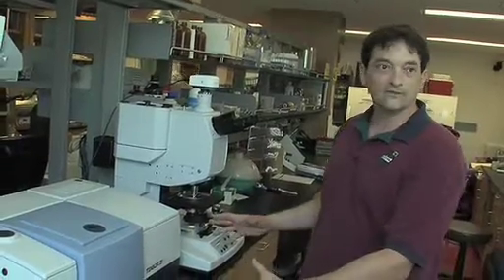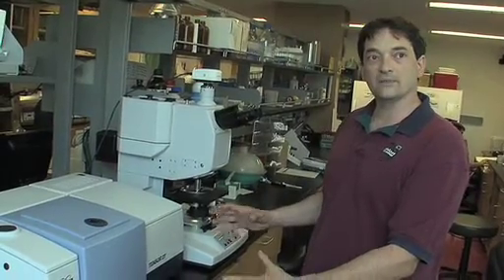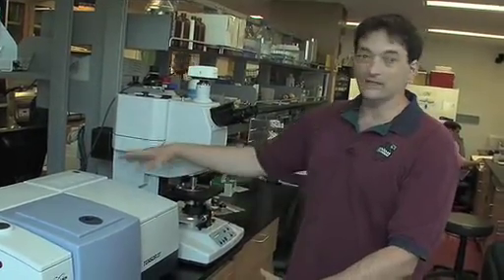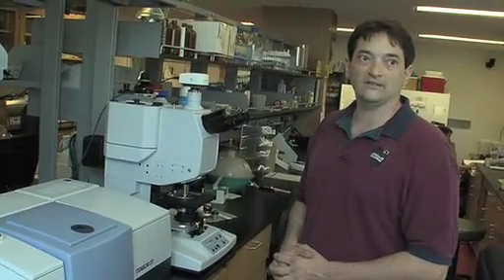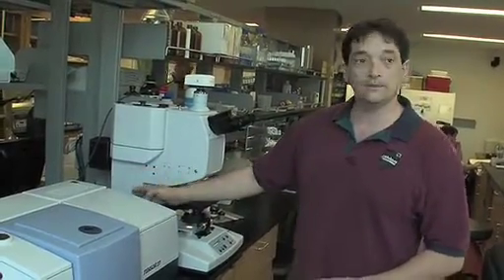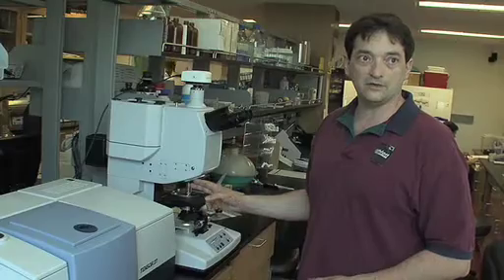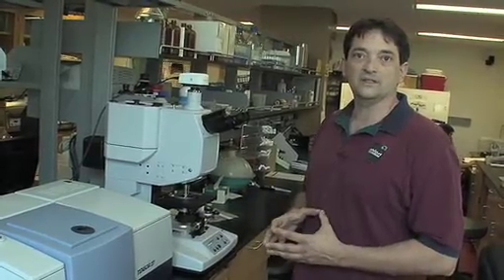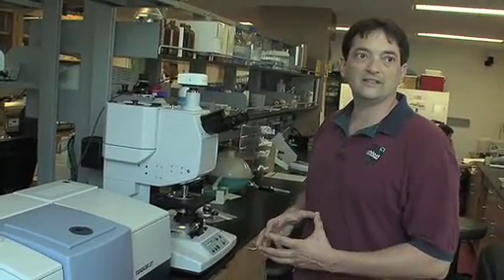So this is our Fourier transform infrared spectrometer, and inside here there's a light source that generates light from 2.5 to 25 microns, and it's piped into this infrared microscope that uses mirrors to focus light instead of lenses that you have in a typical microscope.